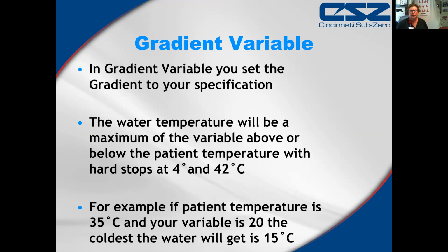So you can go in and hit gradient variable, and you can dial in the number that you want. So for example, the patient's temperature is 35 degrees, and you dial in a variable of 20. The coldest the water will get is 15 degrees Celsius, because we subtract the 20 from the 35. And so the coldest the water will get is 15 degrees. Whereas if we had the patient in the gradient 10 variable, then the coolest the water in the machine would get is 25.